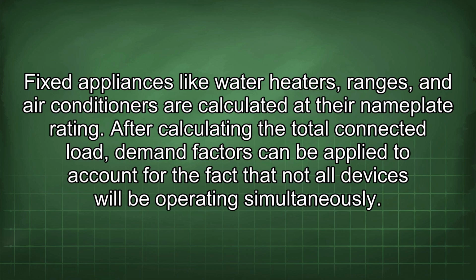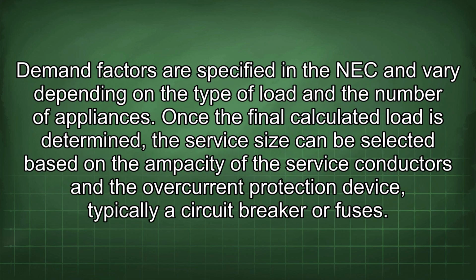After calculating the total connected load, demand factors can be applied to account for the fact that not all devices will be operating simultaneously. Demand factors are specified in the NEC and vary depending on the type of load and the number of appliances. Once the final calculated load is determined, the service size can be selected based on the ampacity of the service conductors and the overcurrent protection device, typically a circuit breaker or fuses.